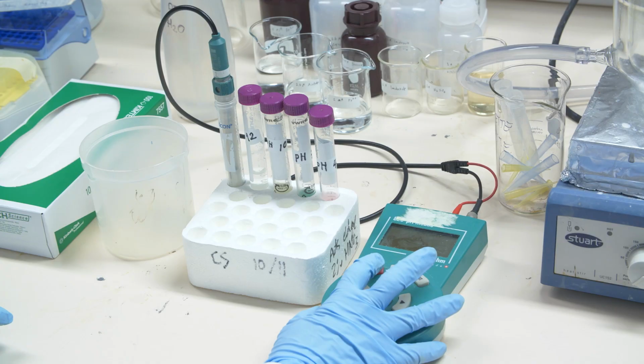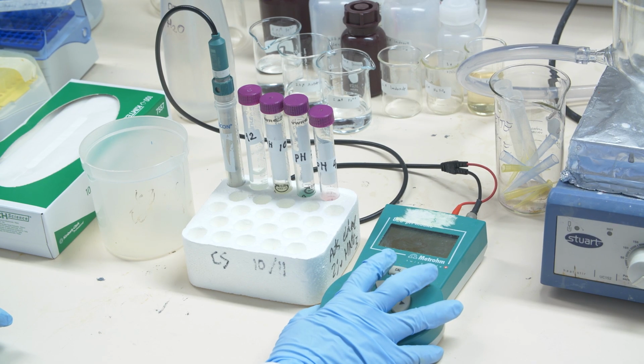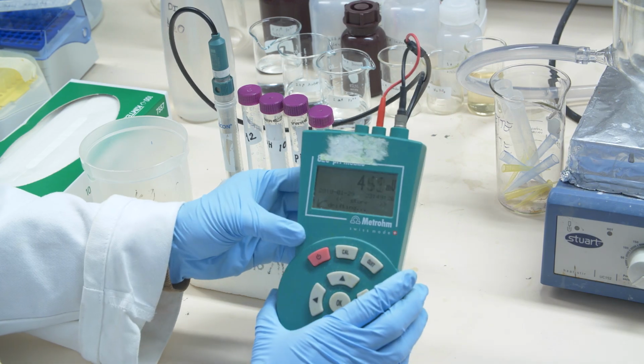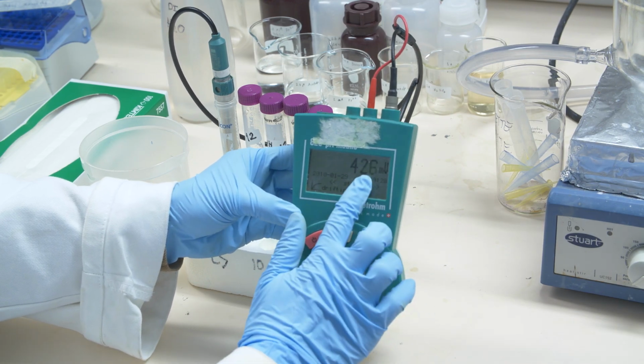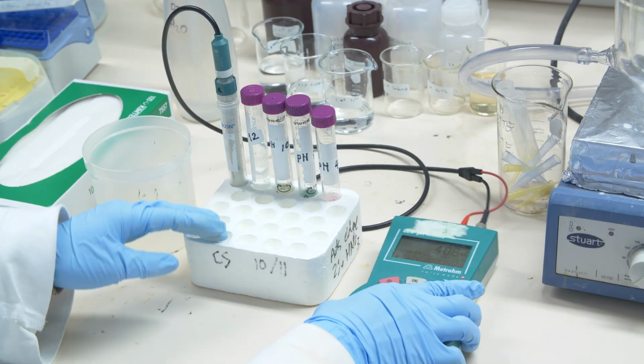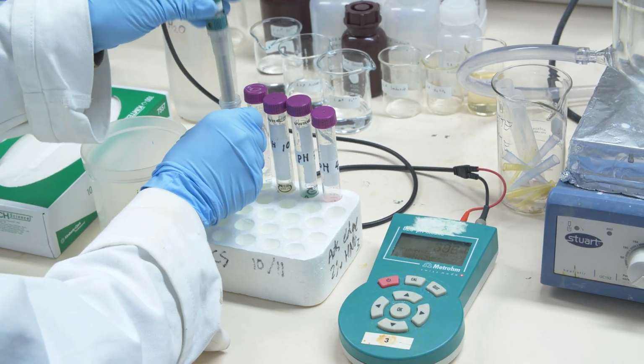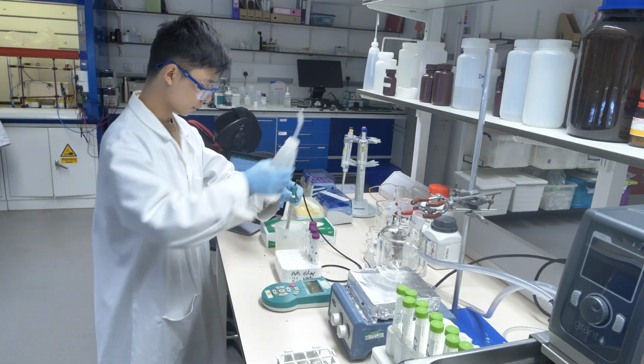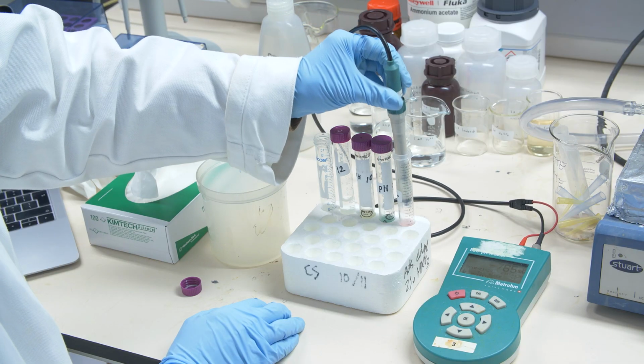The next step is the calibration of the pH electrode. To this end, he uses the Metrohm pH meter, okay, and measures the potential of the electrodes in different standards, different solutions with different proton concentrations and different pHs.